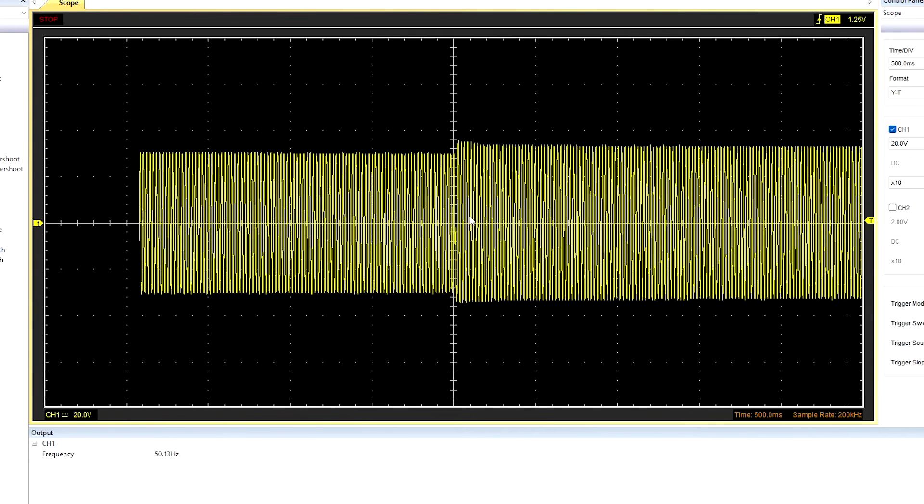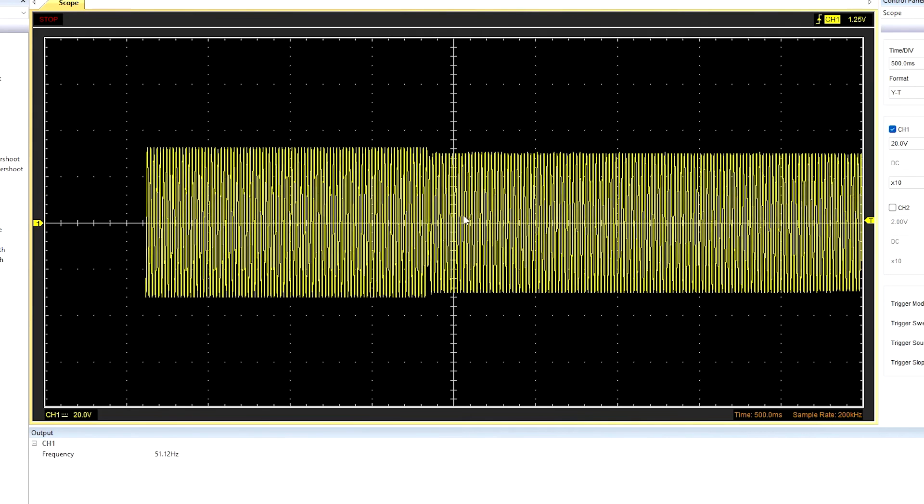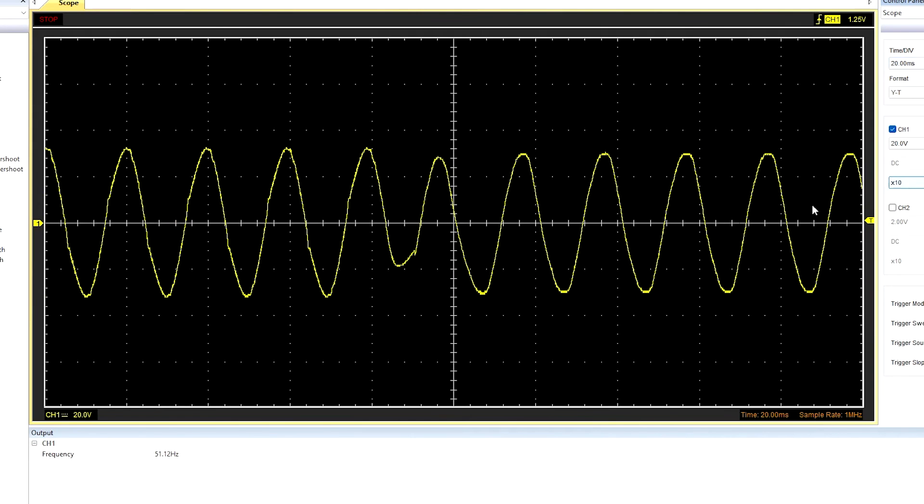OK, here is the switch over point. Mains failure occurred at a positive half cycle, and the inverter started at negative half cycle. The switch over time is approximately 6 millisecond. Let's see once again, inverter to mains, mains to inverter.